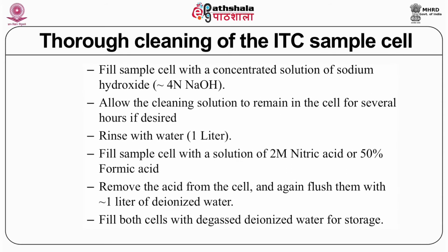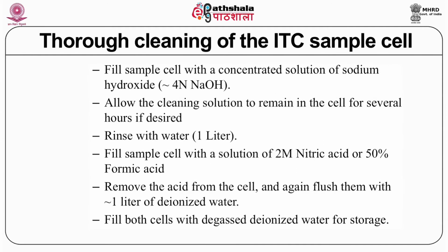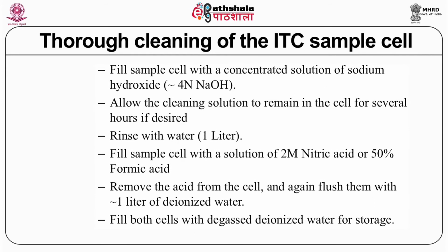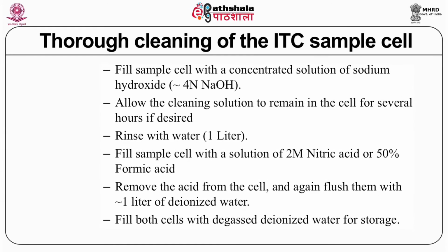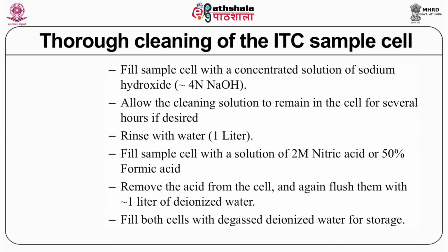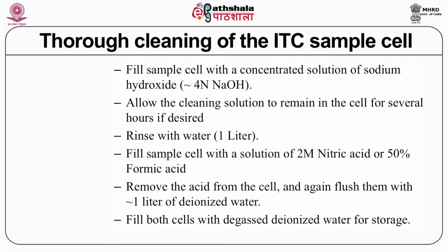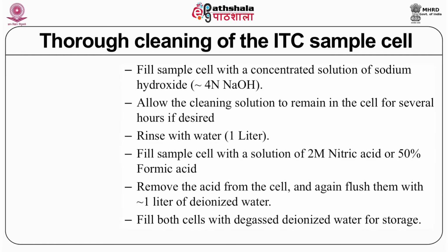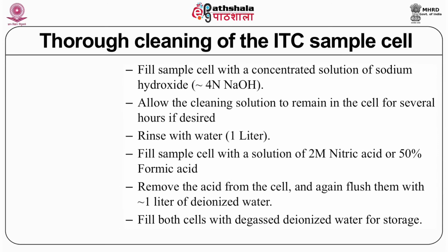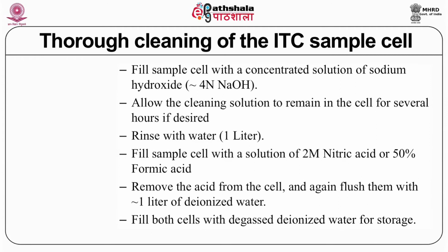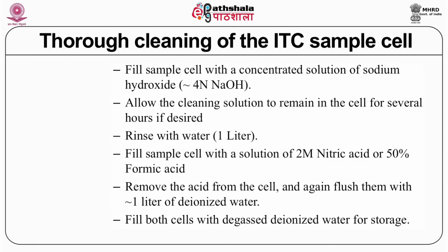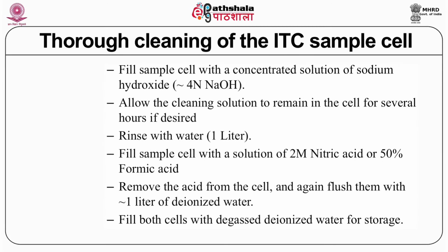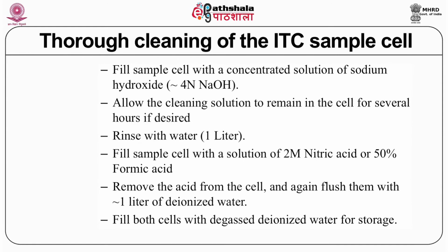So that is why I mentioned a few precautions here: fill the sample cell with a concentrated solution of sodium hydroxide, 4 normal NaOH, and then clean it completely, so that the previous sample, whether it is DNA or a protein, is thoroughly removed, and then rinse continuously with water, as much as 1 liter. The instrument provides that. So you thoroughly clean it so that the previous sample is completely gone.